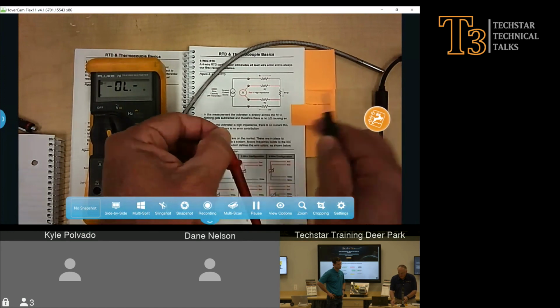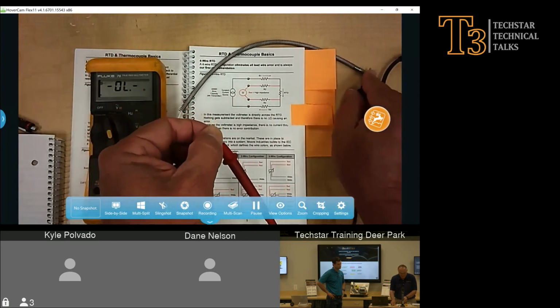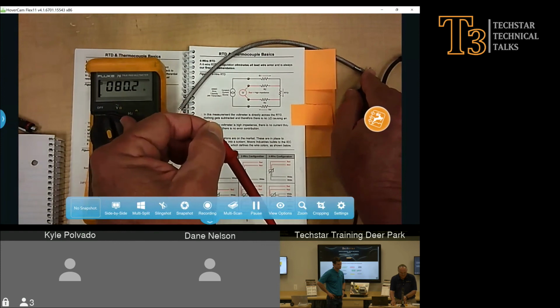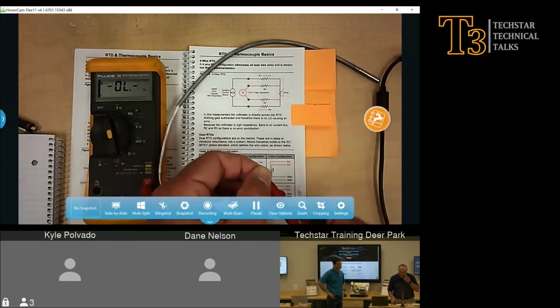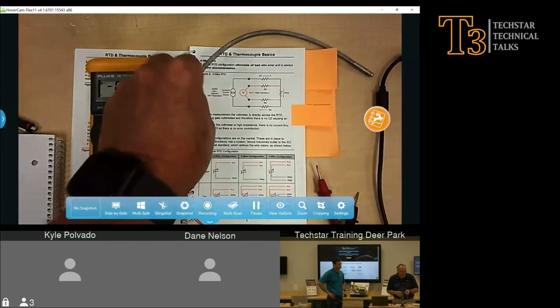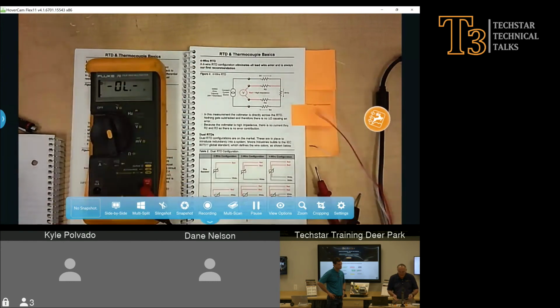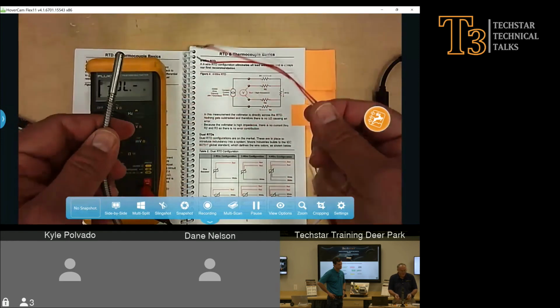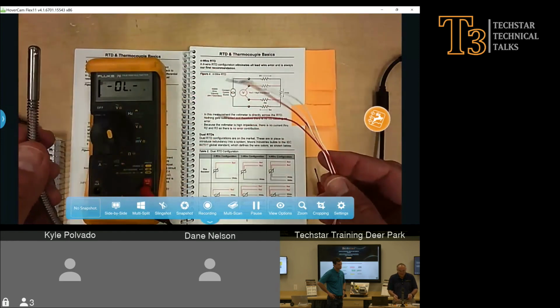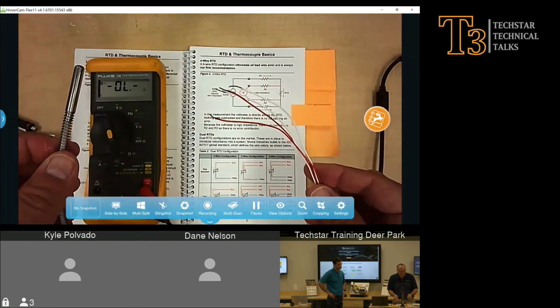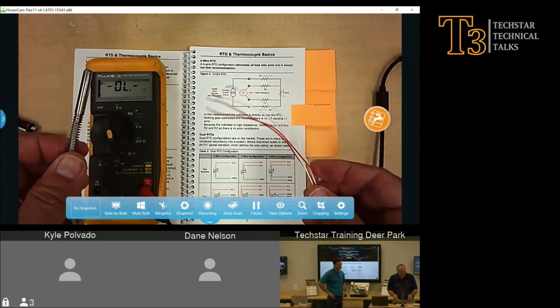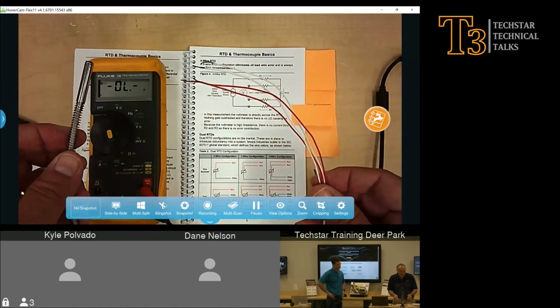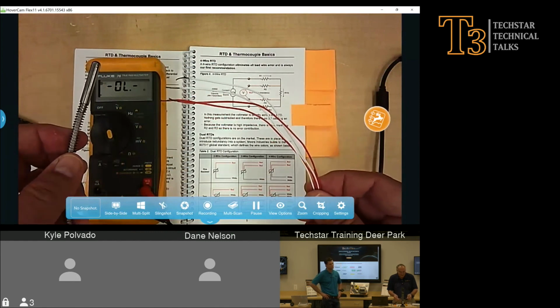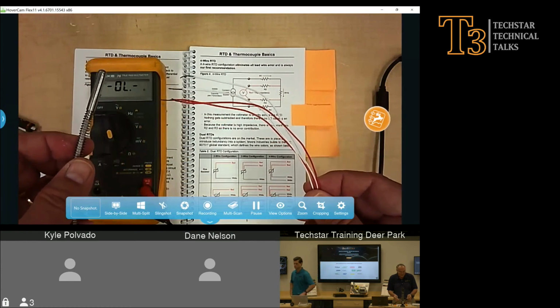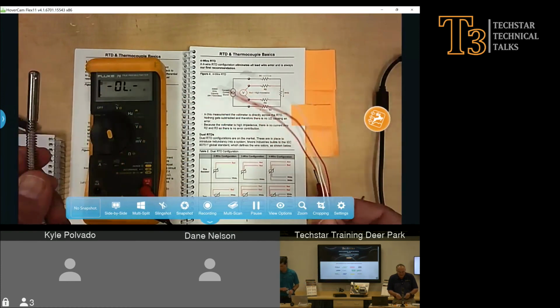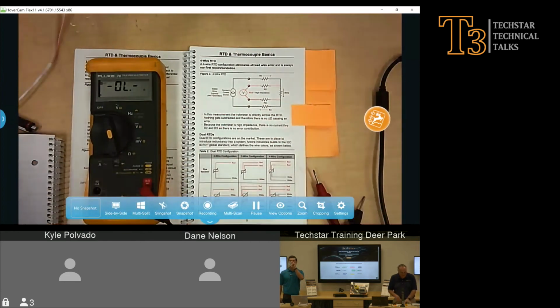And with these ones, still only 80 ohms, so that it should be megohms. So, while this unit appears to work, I probably would call it out, because if you put it in a process, I don't have any power supply in it, I don't have any grounding issues, but there's a good chance that there could be an issue. That's why we always check, even with RTDs, because RTDs have to be floating. If they are grounded, they're not going to work. But if you can break the ground and you have an isolated transmitter, there's a chance that you're going to be okay. So that is for the RTDs.